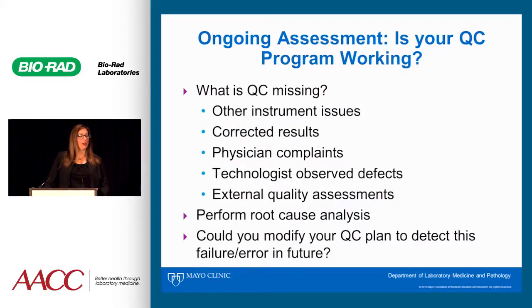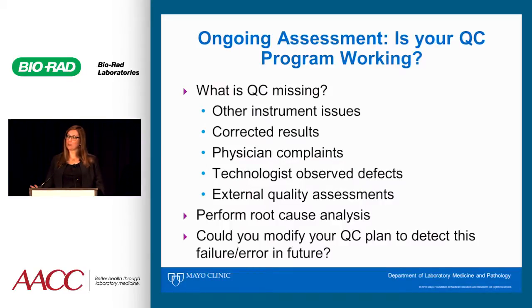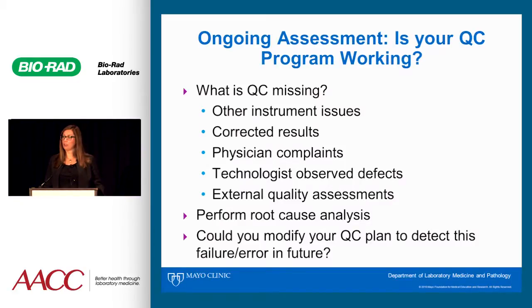Another important question we don't always ask is: what is QC missing? We know what it's catching, but what is it not catching? Are there other instrument issues — results corrected for other reasons that QC didn't catch? Physician complaints? Technologist-observed defects? The techs are the experts; they know what's going wrong in the lab — ask them. External quality assessments: did we fail proficiency testing even though our QC was just fine that day? When we find those issues, let's perform root cause analysis and ask ourselves whether we can modify our quality control plan so that next time this error occurs, we're able to detect it.